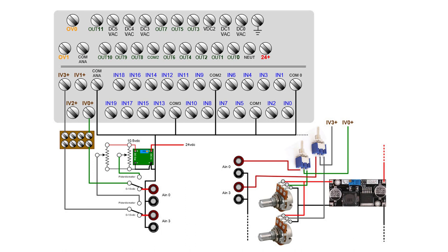We have 2 analog inputs connected to a green and a gray wire, input 0 and input 3. The green and gray wires go to toggle switches that select between 0 volts, 0 to 10 volts DC from a red binding post, or in the up position to the wiper arms on potentiometers that are connected across the DC out of a bucking voltage converter that we have adjusted to 10.5 volts DC, roughly. We're powering this circuit with 24 volts DC.